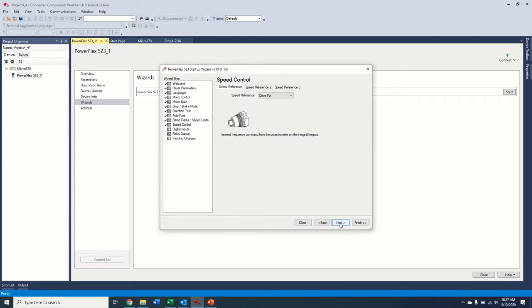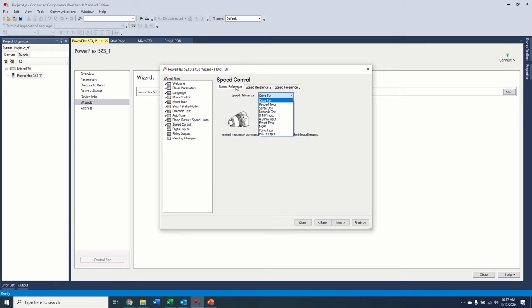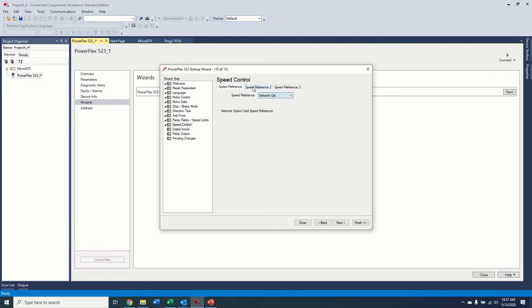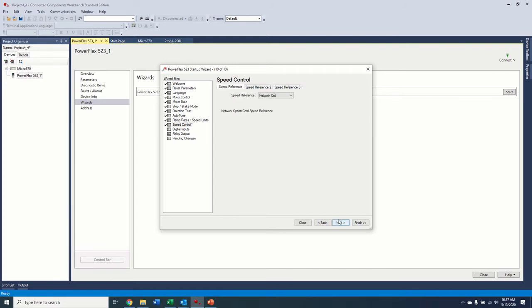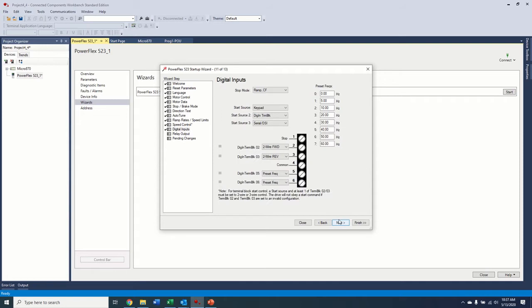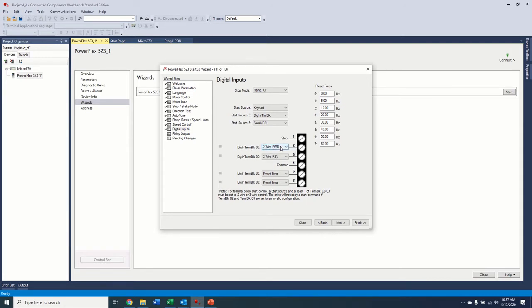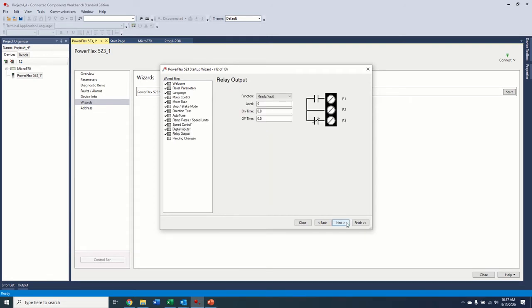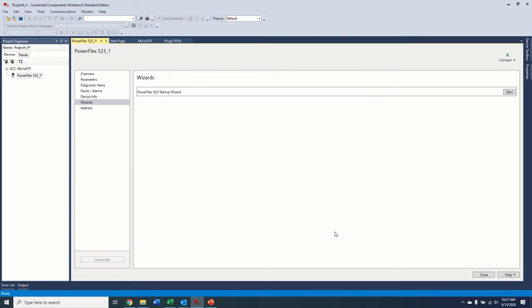All these basic things that you would do on a normal drive startup, you can just step right through. This is your accel/decel and your max frequency. Instead of trying to find parameter 67 and set it to this value and then parameter 62 and set it to this value, it's all very easy to do through here. The drive speed reference, we're going to set to the network. These are the actual terminal numbers on the drive. If you wanted to wire run forward to the drive, you would put it on terminal two. And then also same thing with the relay outputs. It shows you which one's normally open, which one's normally closed on the terminals. And we're going to hit finish.